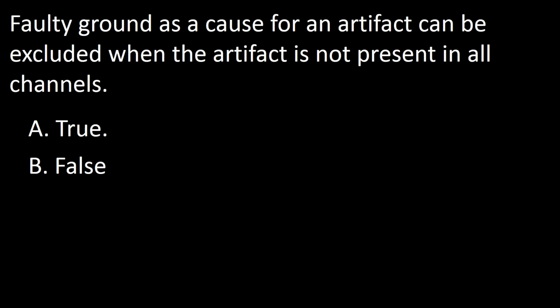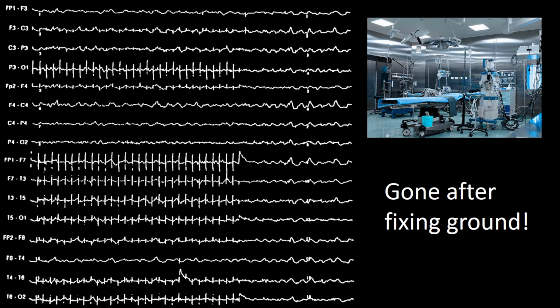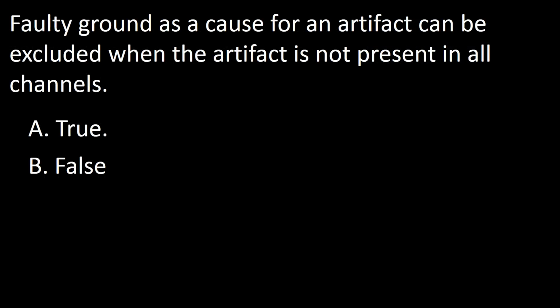Next question. Faulty ground as a cause for an artifact can be excluded when the artifact is not present in all channels. A true, B false. In OR, which is a hostile environment, there are many artifacts. Even if the artifact is present in a limited number of electrodes, a poor ground should always be suspected. So the answer to this question is false.